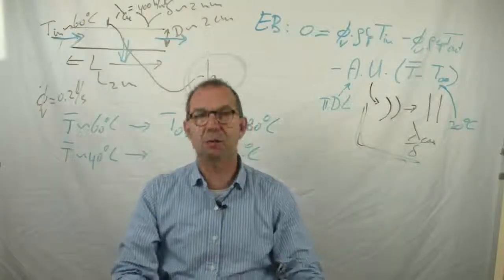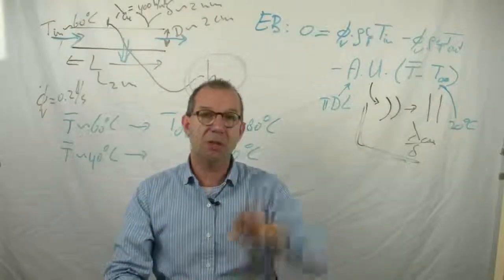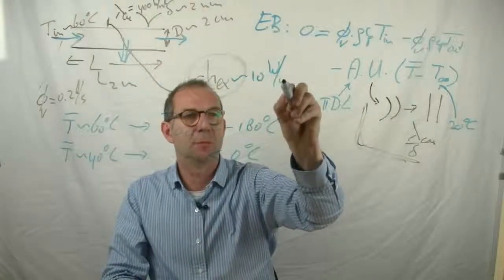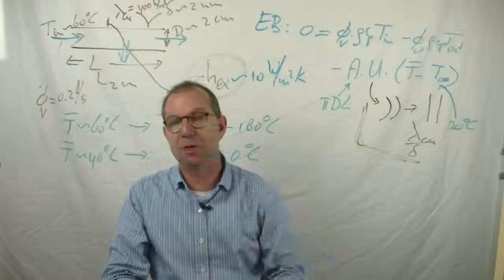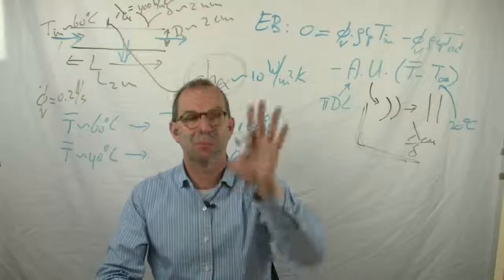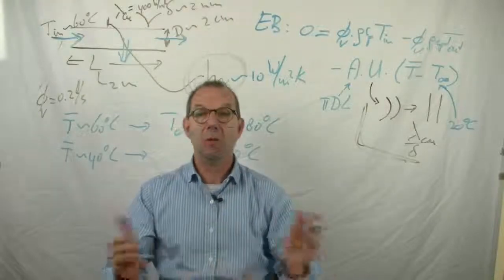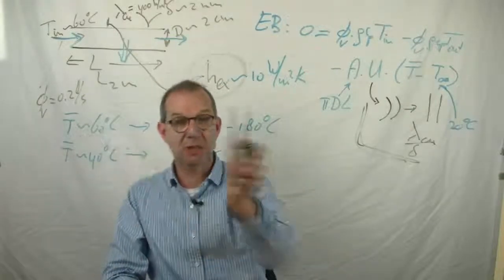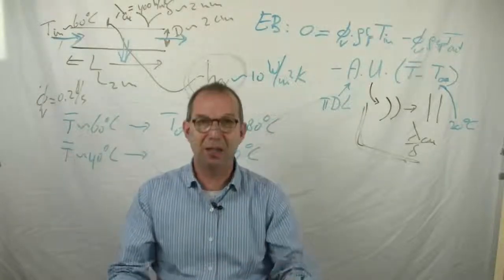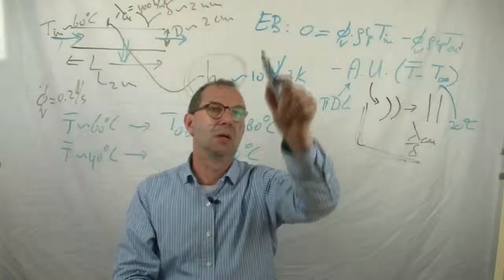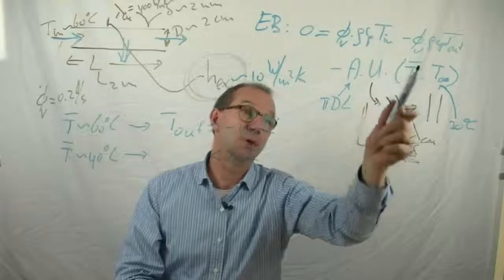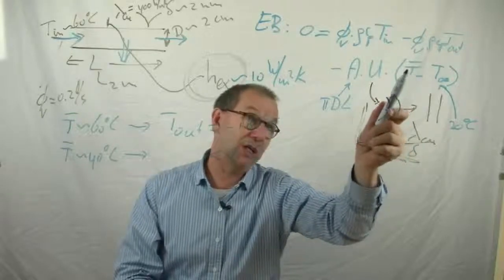So now I need to redo this and think, what if there's an external one, and that is of the order of 10 watt per meter square, a typical value that you encounter in practice for these type of systems. Something that you cannot know, I give it in this example. What will be the consequence? Will we still have to insulate or not? Okay, let's see whether we can estimate what now is the outflowing temperature. What changes here? Yeah, basically U, and thus consequently potentially this one.